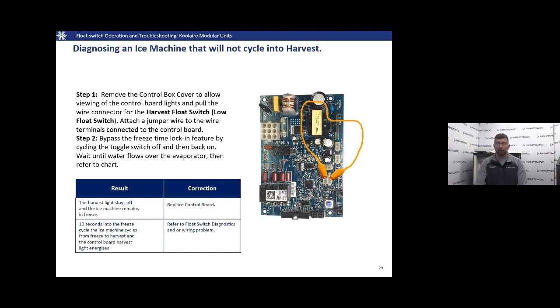For Koolaire, it's a little different because the floats plug in differently. We go straight to the board — remove the control box cover, unplug the float switch from the board, attach a jumper to the terminals on the board, and bypass the lock-in by turning the toggle switch to off and then back to ice. Wait until water is going over the evaporator, then check the same way. If the harvest light stays off and the machine stays in freeze 10 seconds after the pump kicks on, the board cannot see the signal — get a replacement board. But if the machine does go into harvest, you have a problem with the harness or the float itself. Ohm out the float — if that passes, the issue is the wiring harness. If the float doesn't pass, the issue is the float.